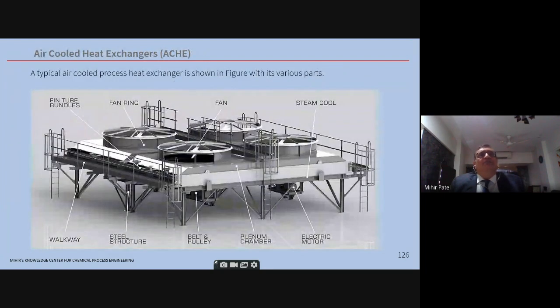Air-cooled heat exchangers. Now these air-cooled heat exchangers again, unlike shell and tube where the thermal design is done, in air-cooled heat exchanger, the thermal design can be done by process engineer. But here there are two things involved. One is the heat transfer area. Other is the fan operating power. So basically you also have an OPEX factor here, operating expenses. Not only CAPEX, you have OPEX also involved. So it is best left to the OEM to decide the thermal design of the large air-cooled heat exchangers.